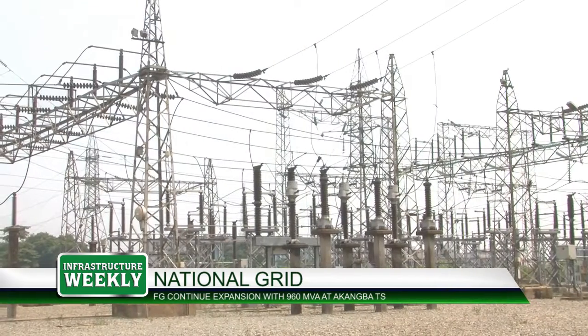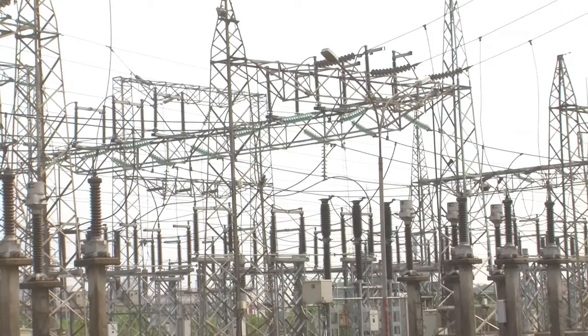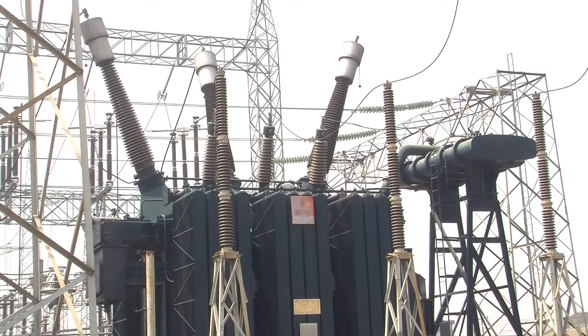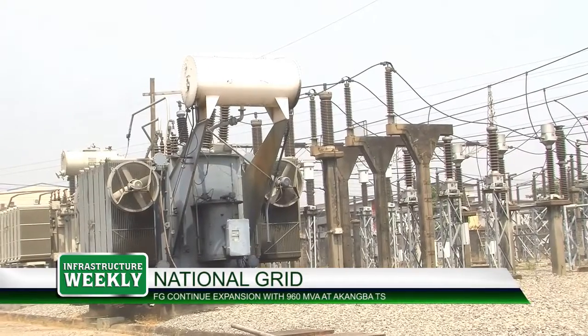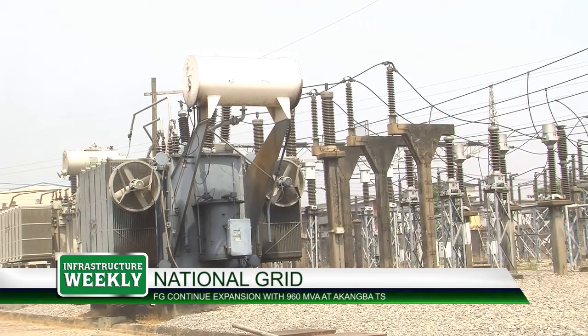When we added this to the total power deliverable to the consumers, it used to be less than 80, but now it's 240 that should go to consumers. And out of that 240, even these 9 feeders are able to take just about 90 megawatts, less than 90 megawatts from the 240. So we still have about 160 megawatts that are looking for consumption, for somebody to take. In other words, with this addition, we still have stranded 160 megawatts of power in this Akangba substation.